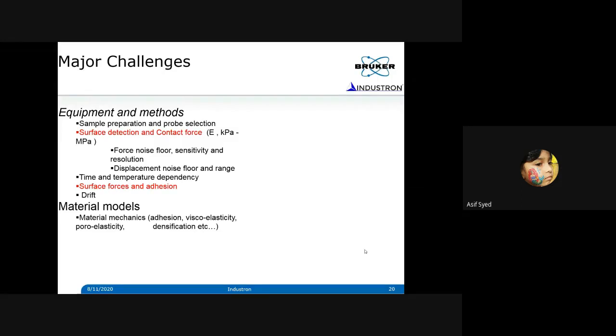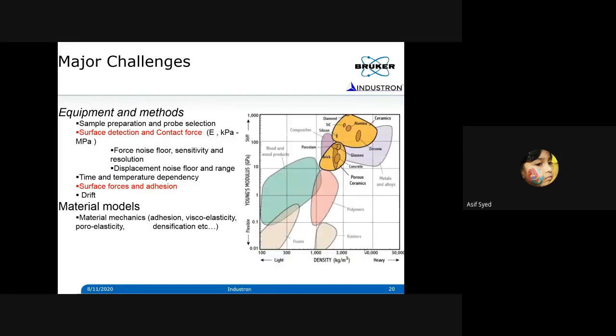So when you do measurements on soft materials, there are major challenges, because the instrumentation that we have developed so far has been for hard materials, metals and ceramics. And when we come to test soft materials, we need to pay attention to many other details. For example, how do you detect the surface of soft materials? For example, how do you detect the surface of water when you bring a probe to make contact, because the surface stiffness is so low? And maybe measuring the surface stiffness of water is easier. Even for some materials, you won't be able to detect the surface of the contact. I mean, when you bring the probe to contact, you won't even be able to sense that. Your force resolution may not be there.